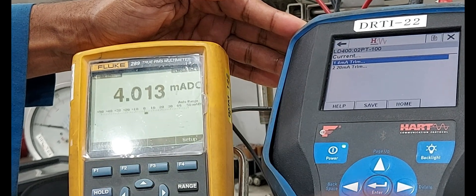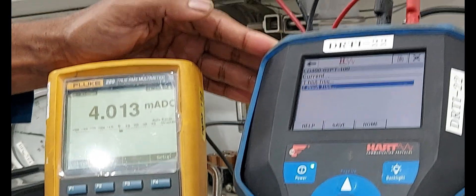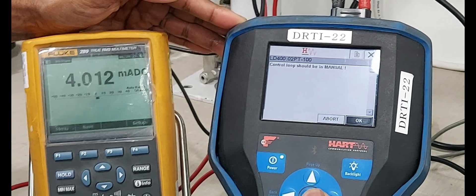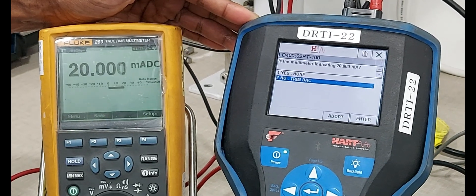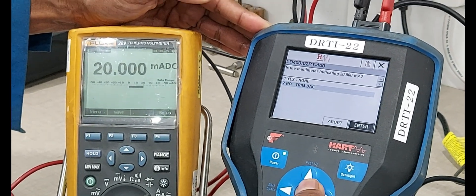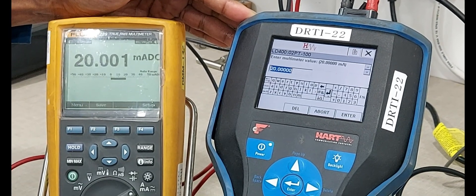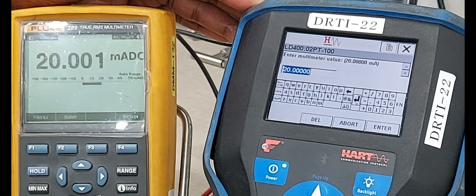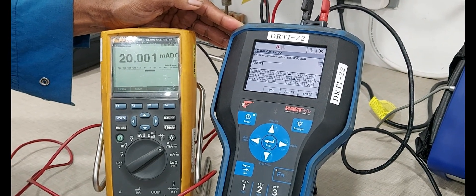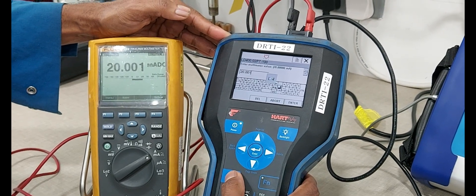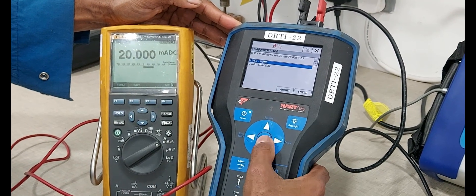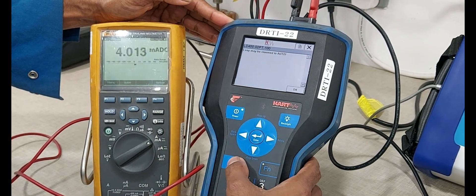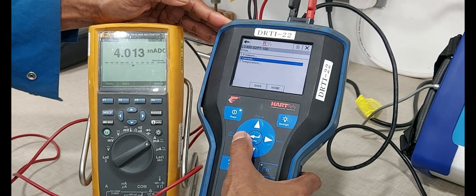Next, upper sensor trim — 20 milliamps. Select the second option. Select number 2. Now display showing 20.001 milliamps. End of it. Now it is clear. Now in auto mode. Back.